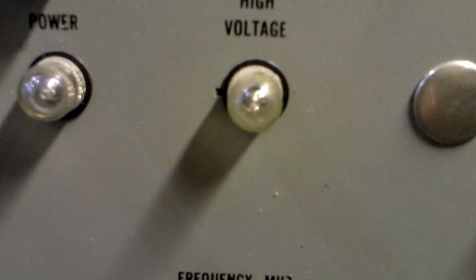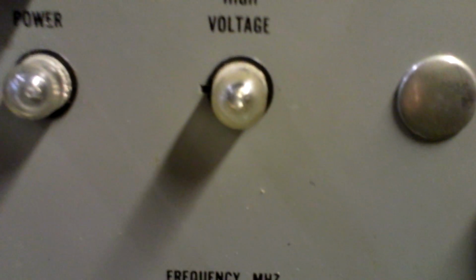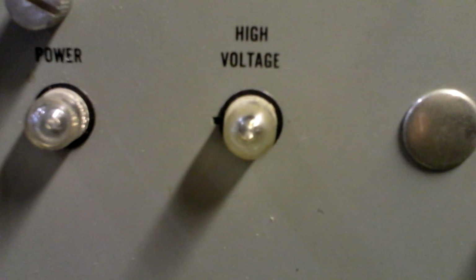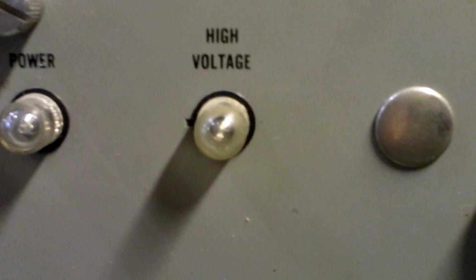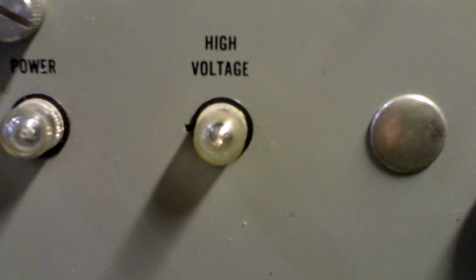The high voltage indicator will come up after 3 minutes after this is powered on. Once primary power comes on, it takes 3 minutes, allowing time for the tubes to get to full temperature before the high voltage comes on.